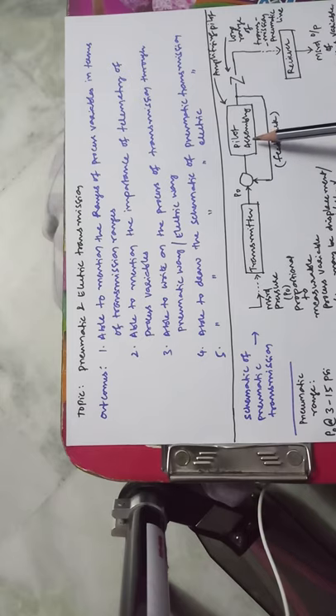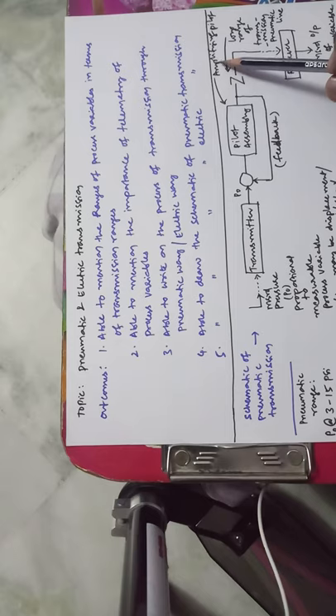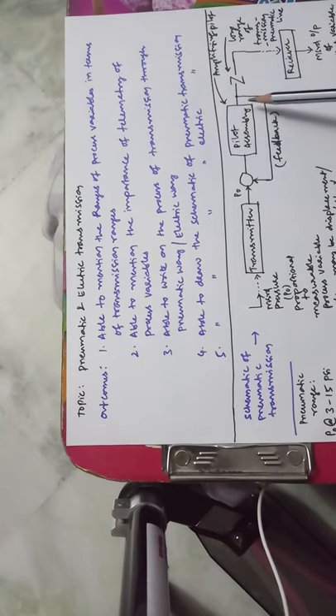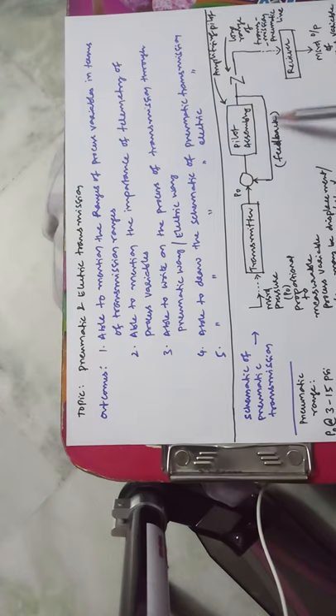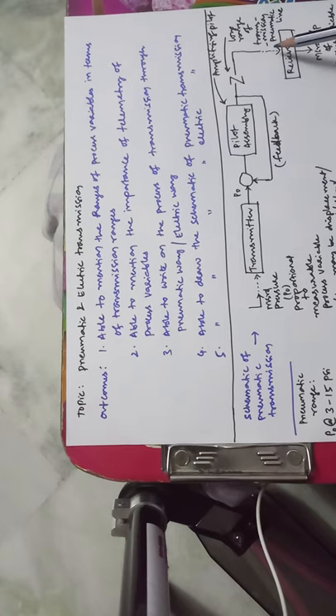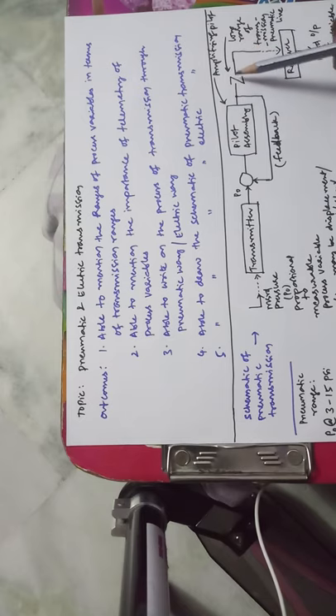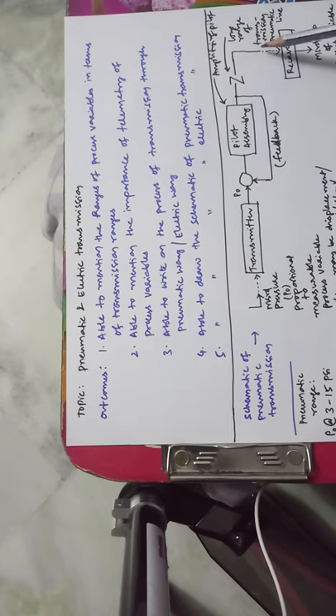To improve the signal, we can have a mechanical amplifying system referred to as a mechanical pilot assembly or amplifying pilot, which boosts the pressure signal. There is a feedback mechanism to ensure the signal is properly amplified. The symbol Z indicates a long-range transmission pneumatic line.